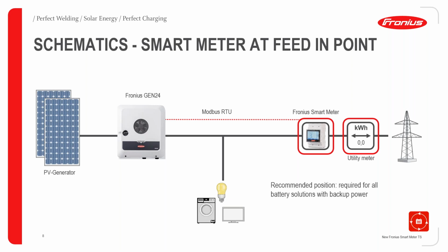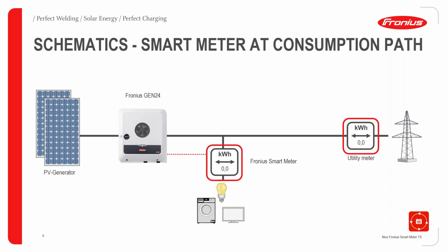And then there is another place you can also install this smart meter, that's called the consumption path. You can put it right before the load or any consumption. In case for some reason it is not possible to install it in the feed-in path, you can also install this in the consumption path. But remember, there is a difference between the feed-in and consumption path. You cannot measure everything, where the energy is coming from, whether it is from the PV or from the grid.